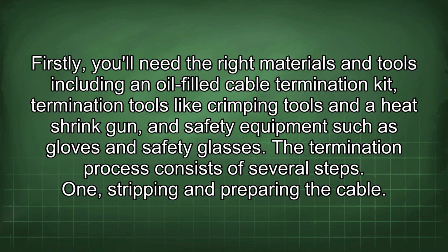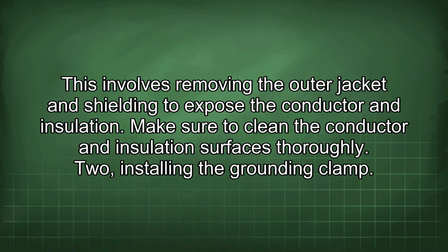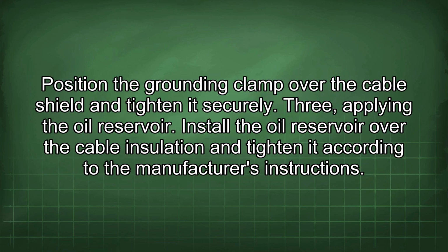The termination process consists of several steps. 1. Stripping and preparing the cable. This involves removing the outer jacket and shielding to expose the conductor and insulation. Make sure to clean the conductor and insulation surfaces thoroughly. 2. Installing the grounding clamp. Position the grounding clamp over the cable shield and tighten it securely.